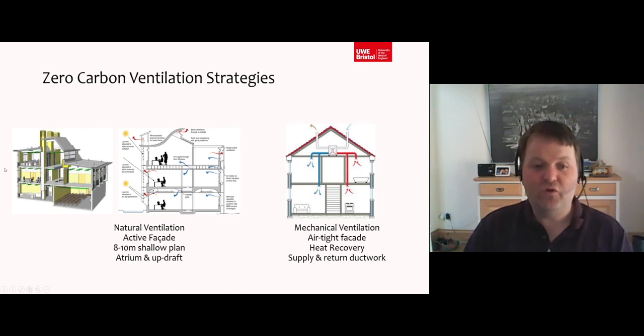And then when you have that sufficient draw, you can then pull air through these rooms and into the building by automating a window, opening a window, or like we have in our block, behind the radiators there's a louver, a very quiet louver that opens up and closes automatically, and that will be determined with the sensors in the room, measuring CO2 levels for freshness, measuring temperature for comfort, and determining what level the windows need to be open, and that draw then is released. We have 7 big chimneys in our block that are doing just one half of the building to the north, and then the spaces to the south are being done using the atrium up here through the middle. Again, most are just done by an atrium, and this top hat section is the section that actually causes that draw in the first place, which again pulls that ventilation level through.